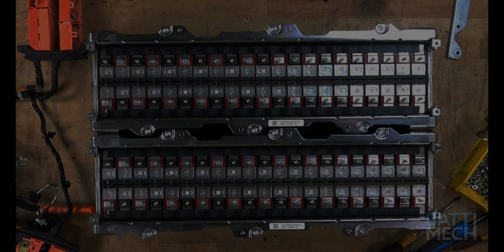These highlighted areas show where the removable positioning bolts should be located. The battery has 2 battery blocks on the bottom layer and 2 on the top layer. Any battery blocks with these positioning bolts should be installed on the bottom layer. These bolts are only used to help position the top layer battery blocks onto the bottom layer. Note: not all battery makes and models include all 4 bolts.